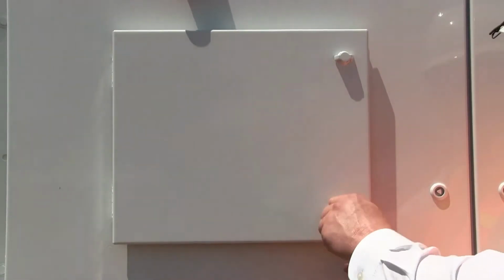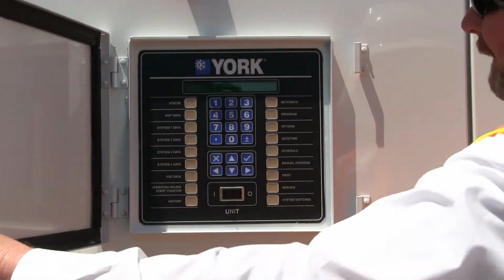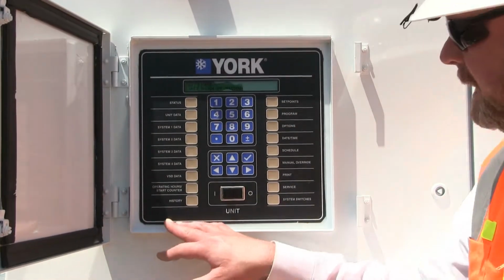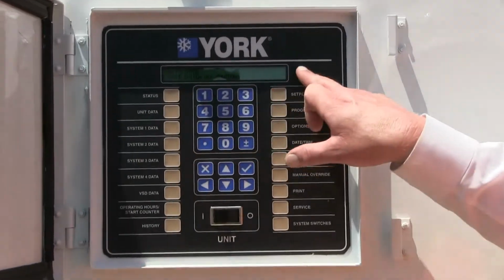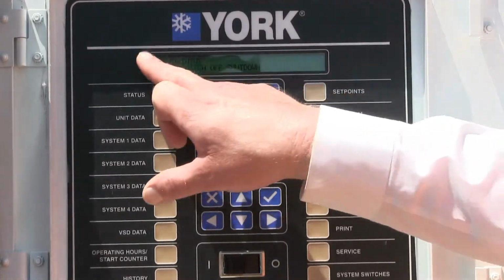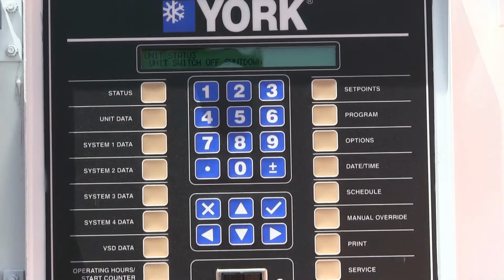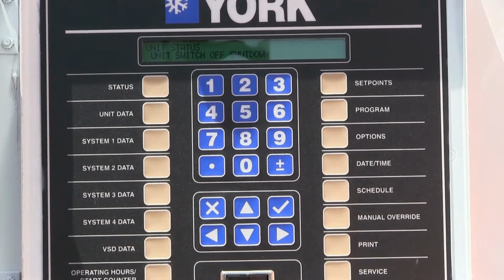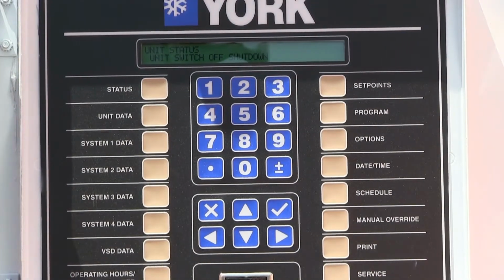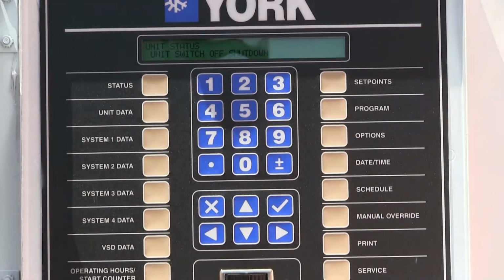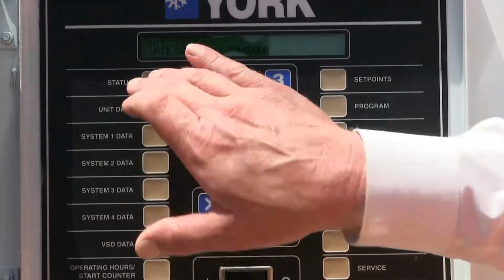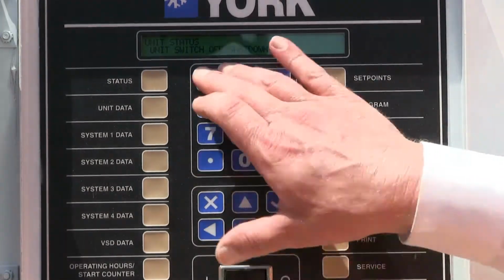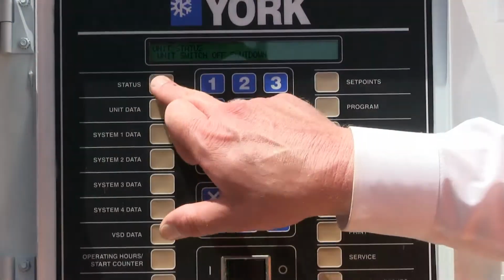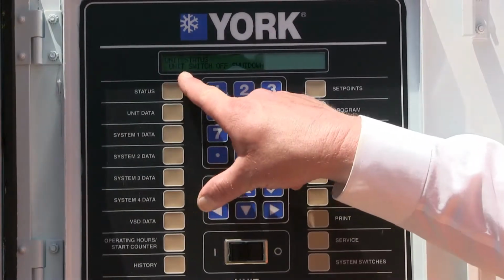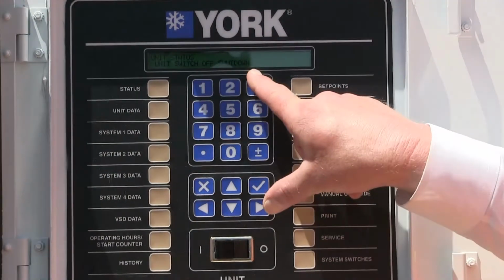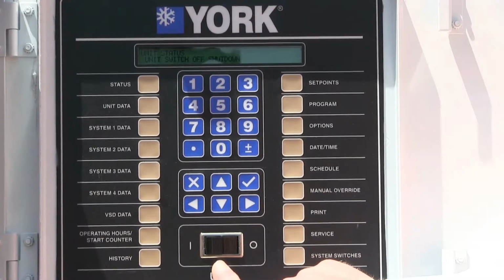Okay, we're going to first start by opening up the control panel door here. And you'll notice that, first of all, our keypad in here, this is our status screen, our LCD screen, at any time tells you values of the chiller, what the chiller's doing, the operation. It's basically your user interface. So I'm going to take a moment to go quickly down through the buttons here. First off, don't worry about pushing any of the buttons and hurting anything, because you're not going to. You just go back to your main status, and it tells you right now that the unit switch is in the off position. That's this switch here.